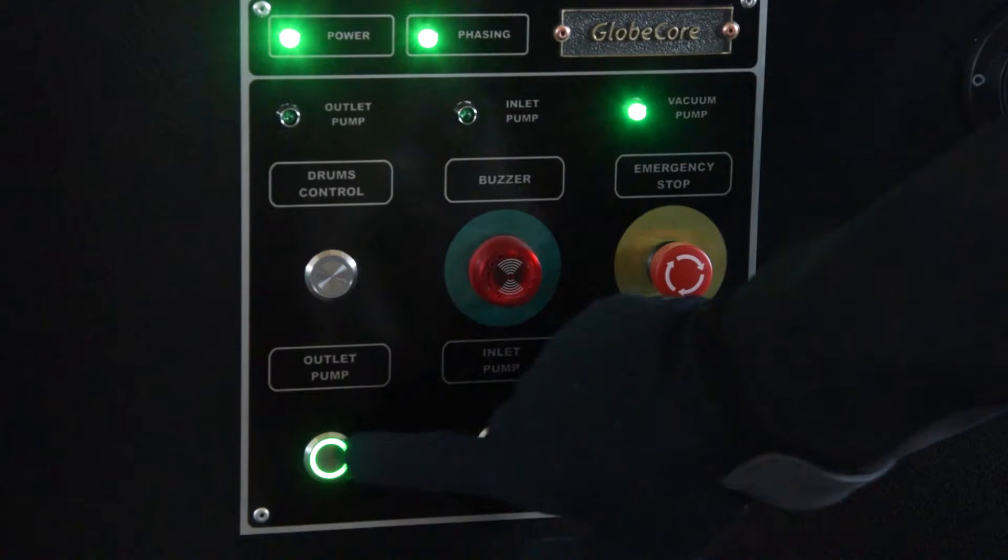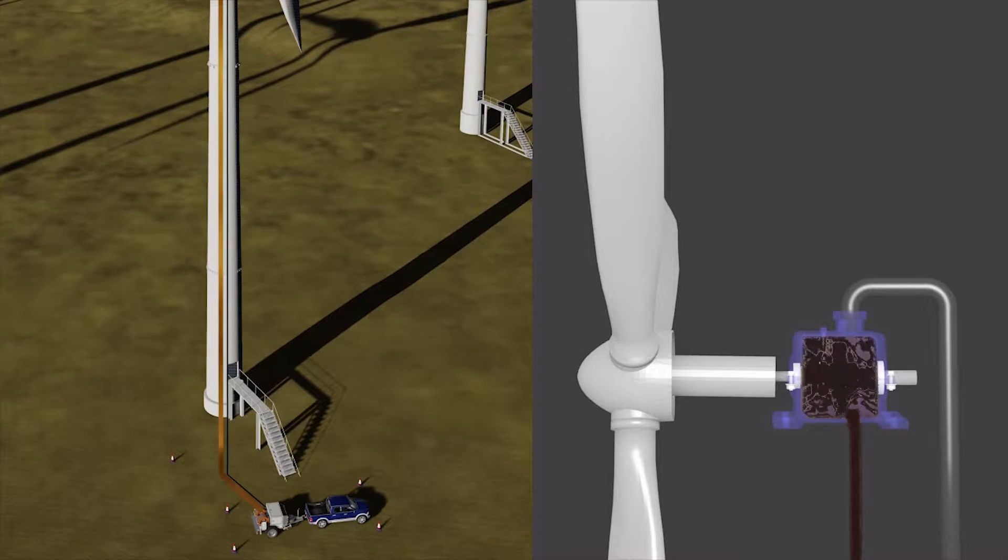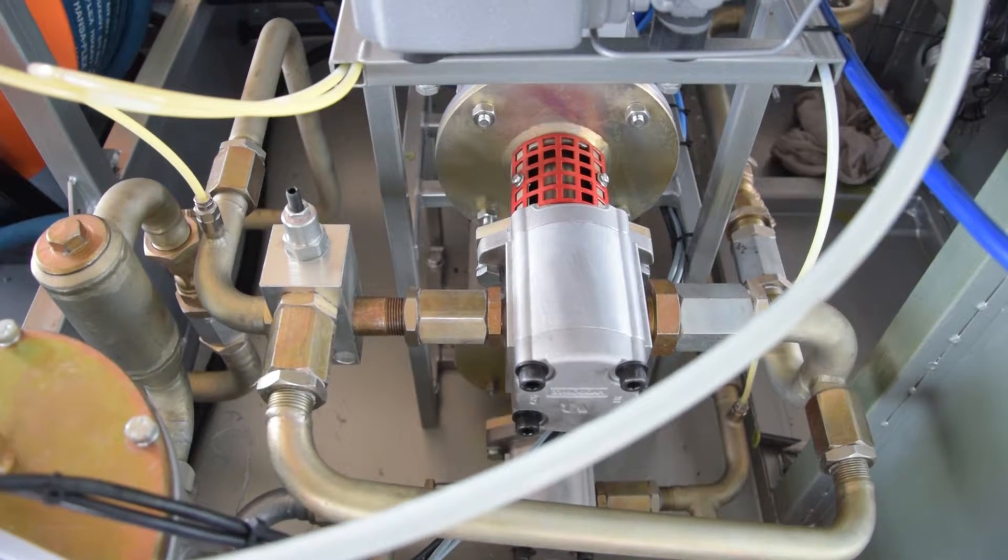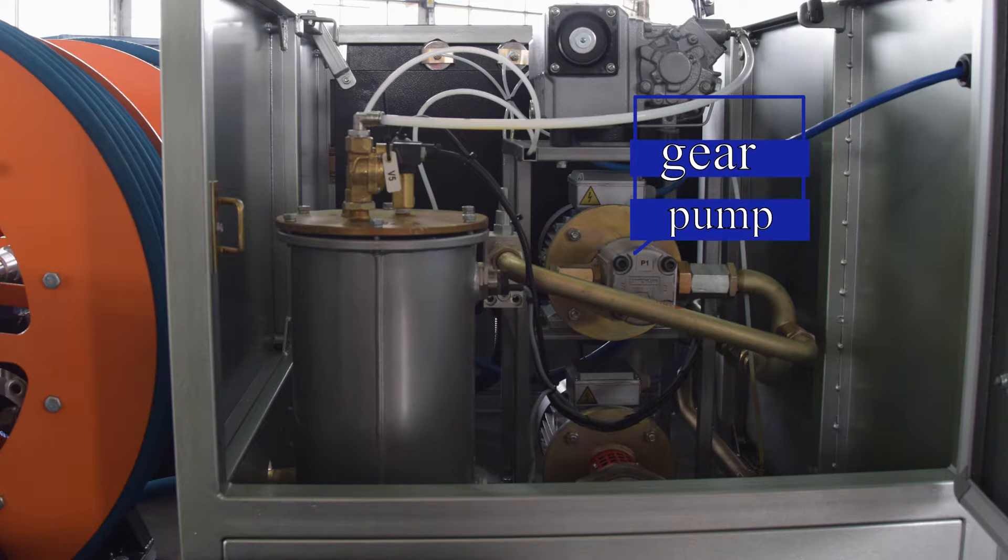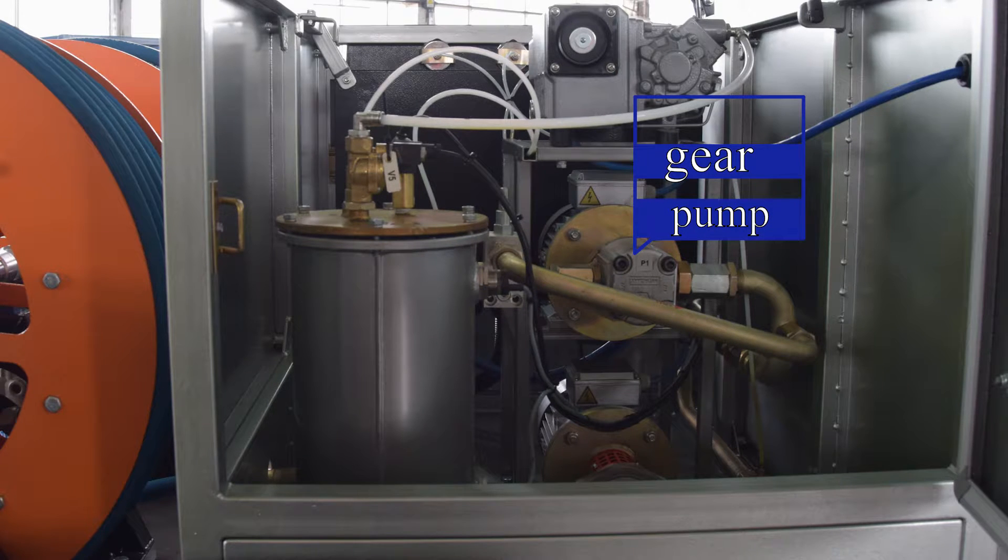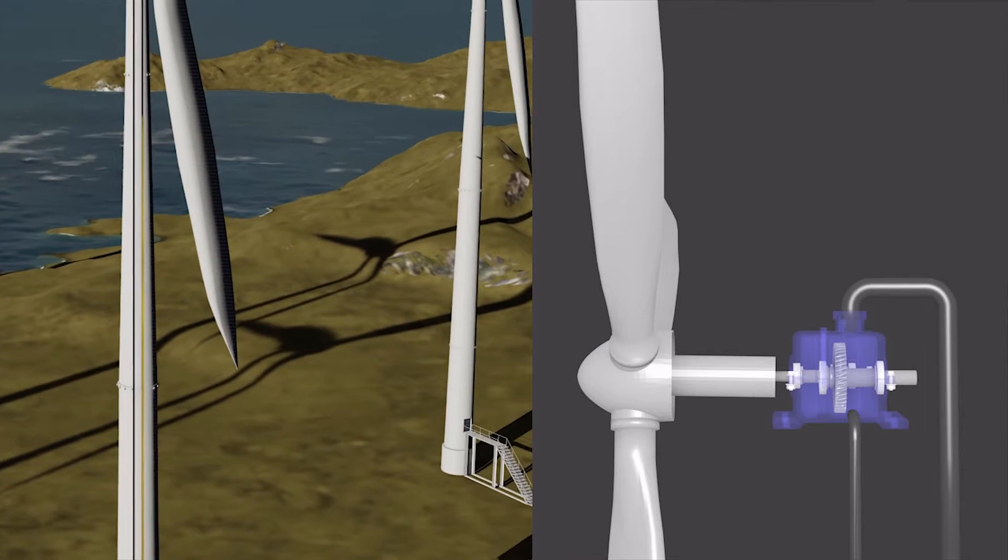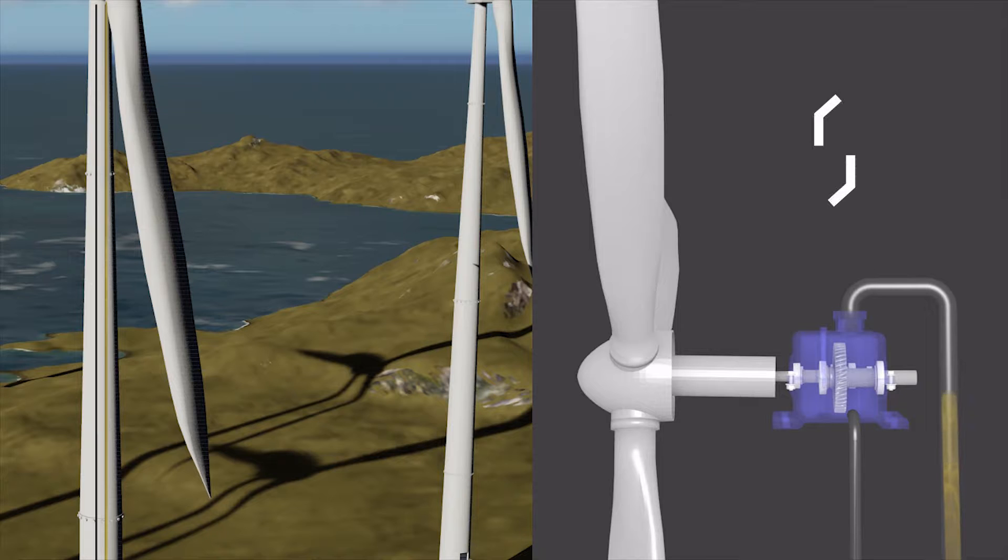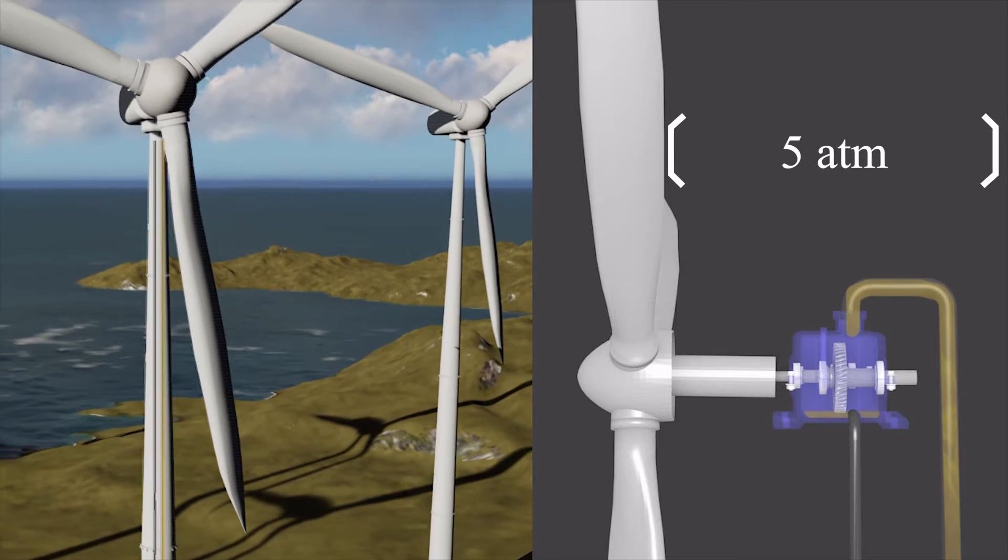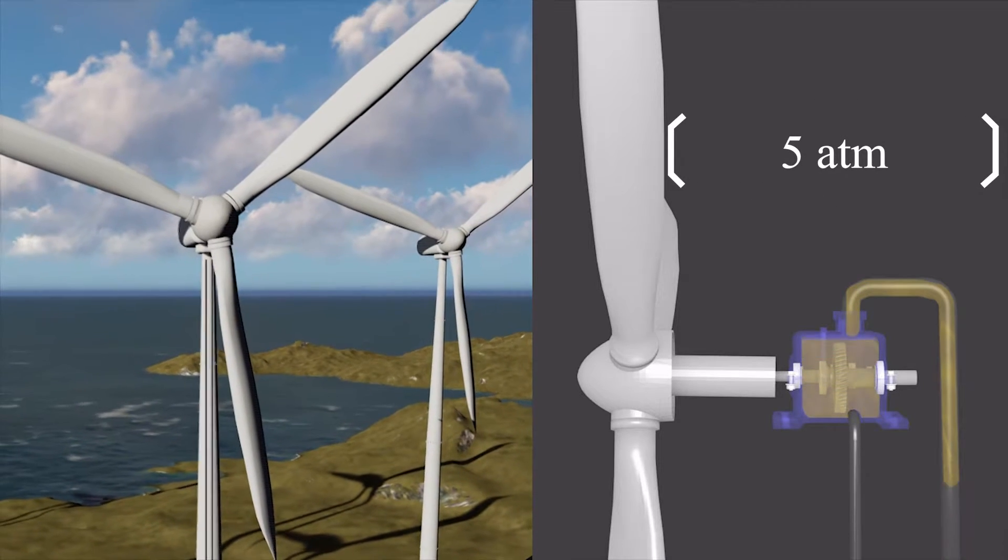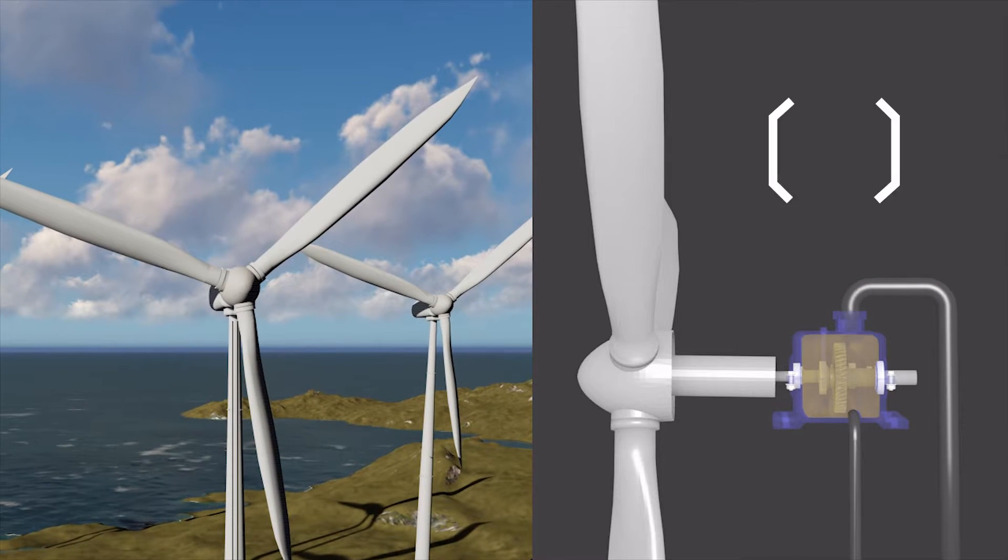The mode of flushing a gearbox with flushing oil: In this mode, the gear pump feeds the flushing oil to a specified height up to 60 meters at a pressure of 5 atmospheres and pours it into the gearbox housing, flushing the residual used oil and mechanical impurities.